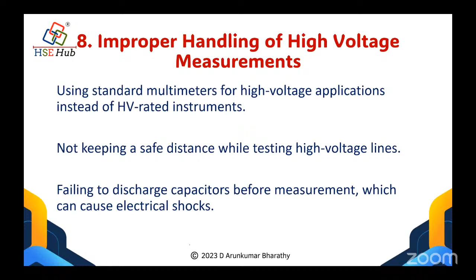So what are all the things we discussed as of now, if summarized? There are many processes in electrical safety. One process which is not given regular attention is the testing and measurement process, because any electrical circuit must be tested before touching, but the testing process also must be safe. For that, we talked about the traditional voltage measurement system, the normal tester and the impact of using it for other purposes, and even with the proper instrument, when it is not used correctly, when the correct range is not selected, and when it is not handled properly with the probes and other accessories. Then, when it is not correctly selected for high ampere measurement, accidents are inevitable. So that is the point we saw as of now.